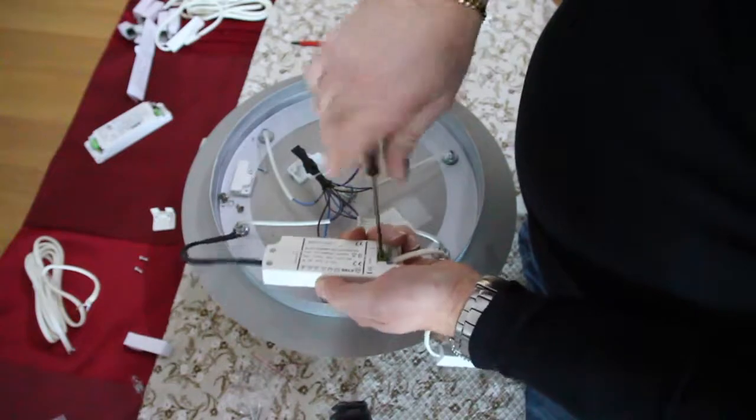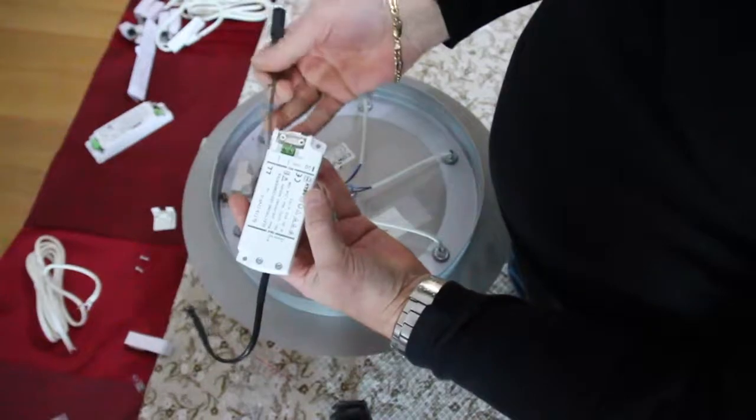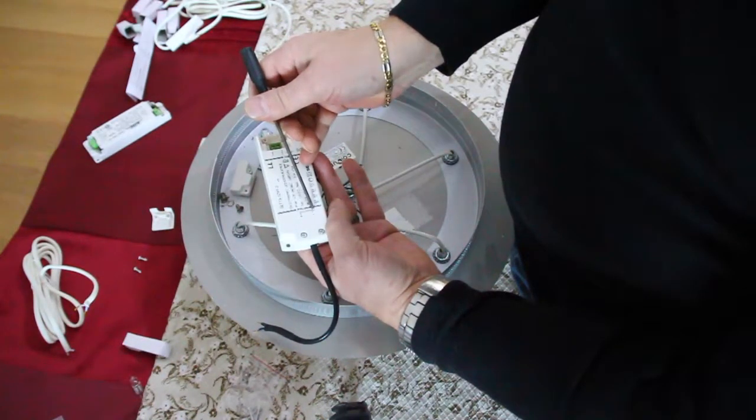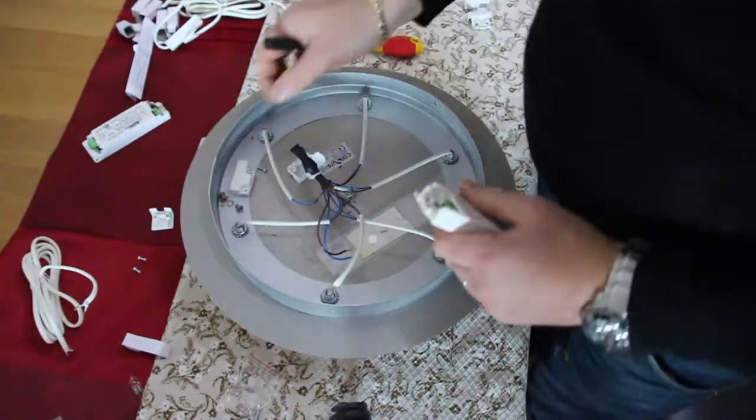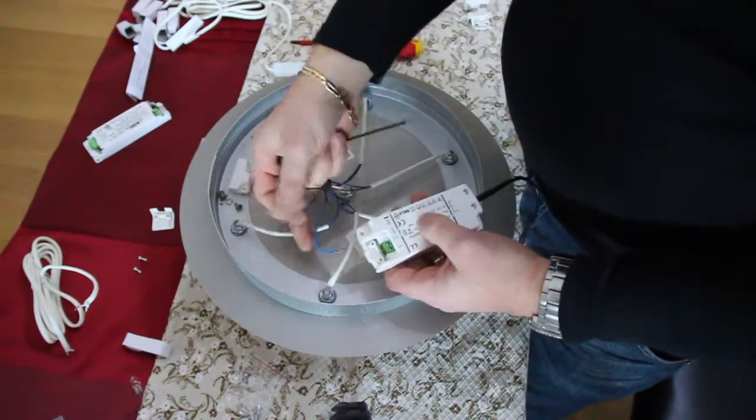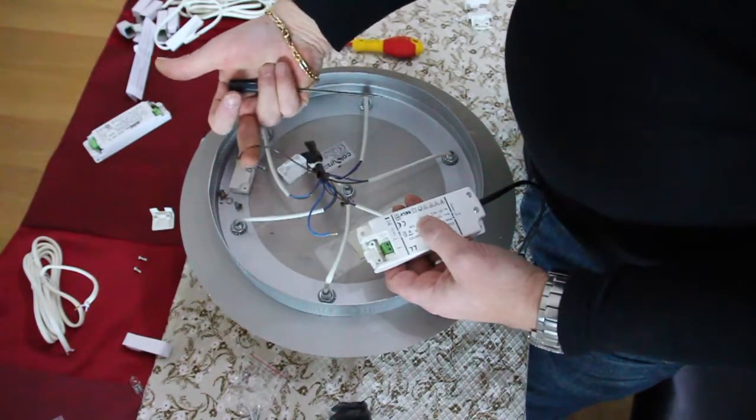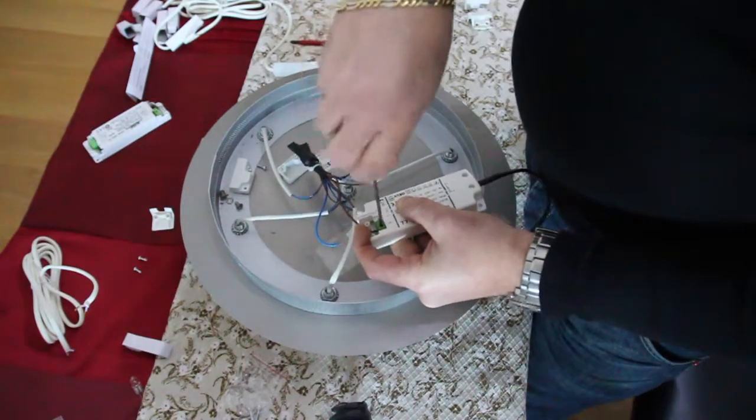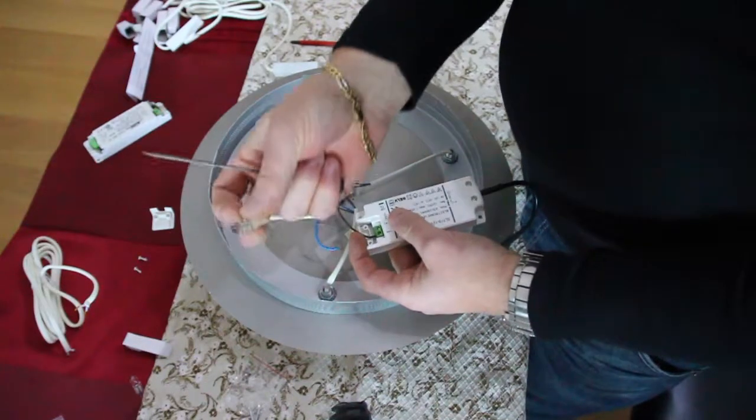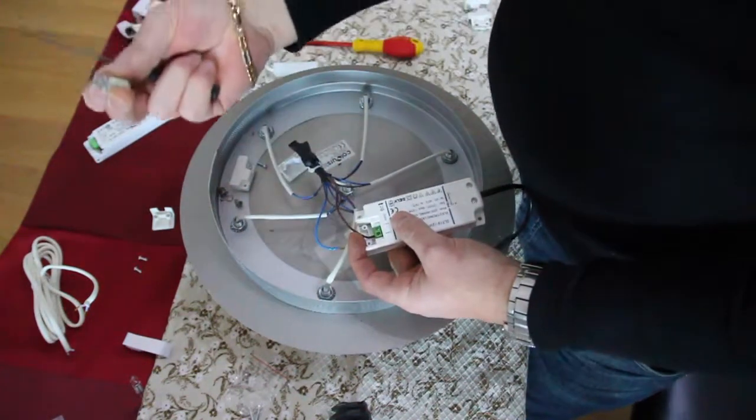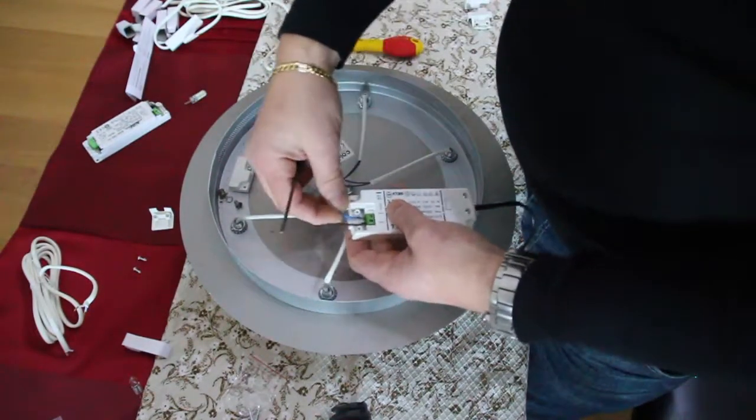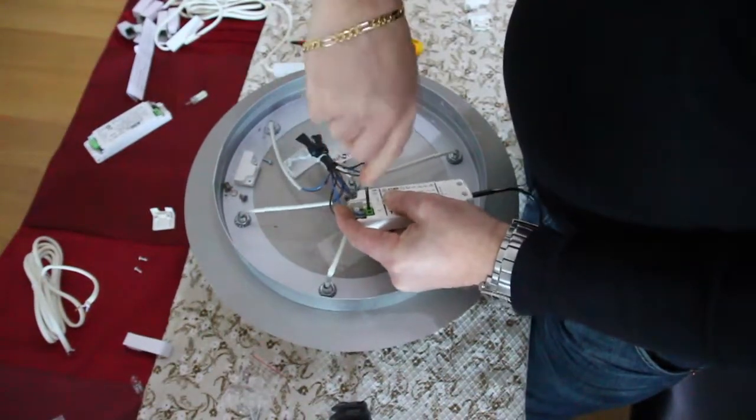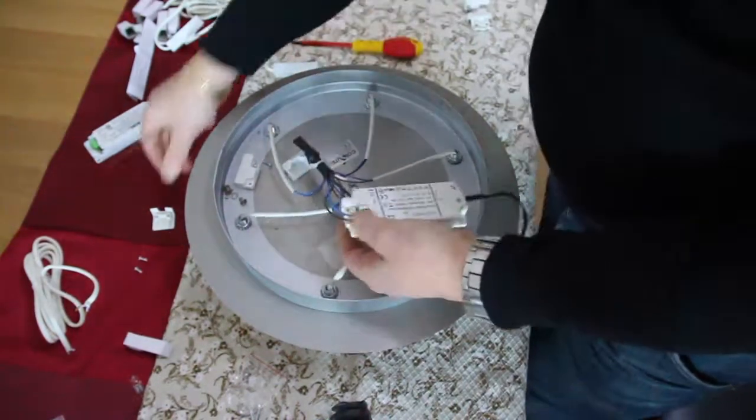So we're going to remove from here the secondary or the 12 volt output, and always double check that you can see on there. 12 volts DC for our secondary and on the other side just to confirm 220 to 240 volts AC on our primary side. Okay, so now we've got our feeds out to our lamps. So I'm going to connect those in the same manner. I would advise that be done in the event you get LED lamps like this that require polarization. In other words the positive to be fed to the positive pin. Some do, some don't. These are happy either way around. But if you make sure that your wiring follows through in the correct colors and the correct polarities it'll make life a lot easier for you. Okay, again we make sure they're fully inserted. They're nice and tight and we can put our cover back on.